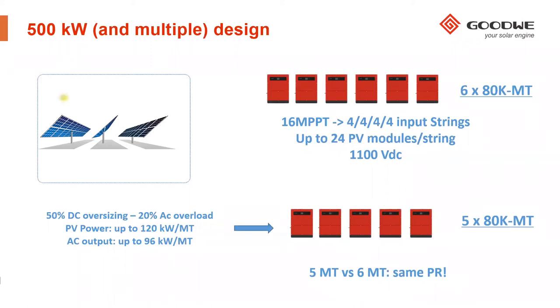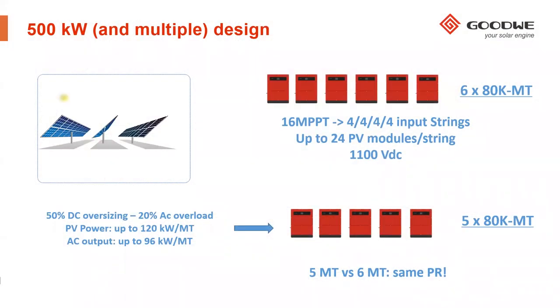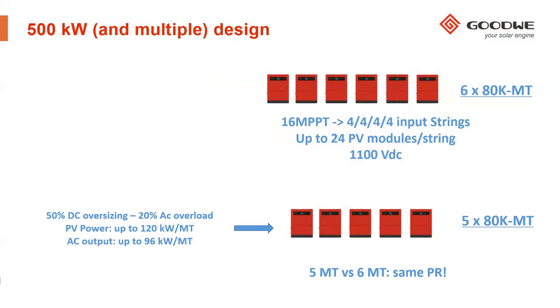What you can see here, what is our proposal? We basically offer to use 6 devices of 80 kilowatt. With these devices you have available 16 MPPT to be used with 4444 input strings, which means 4 strings for each MPPT. This gives you a high level of flexibility, it's clear.